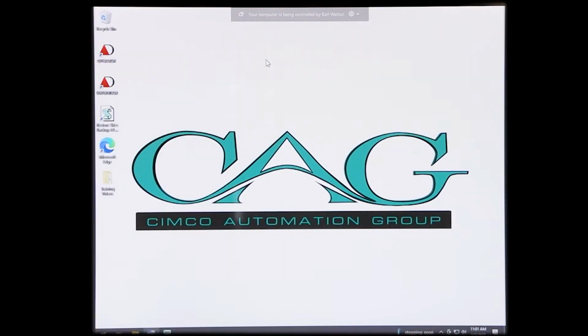Okay, so this portion is the computer training. This home screen is a mimic of the touchscreen downstairs in the panel. As we have talked about before, you have 2 variations. You have operator, which is read-only, and you have supervisor, which is to log in to make all your temperature changes to your sheet, look at your trend logs, everything else. You can also look at your trend logs under operator, because there are no settings to be changed within the trends, but you can see them there.